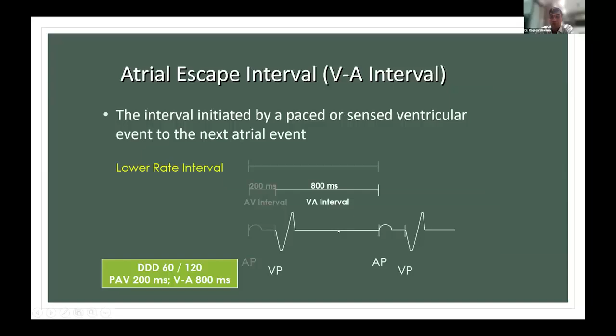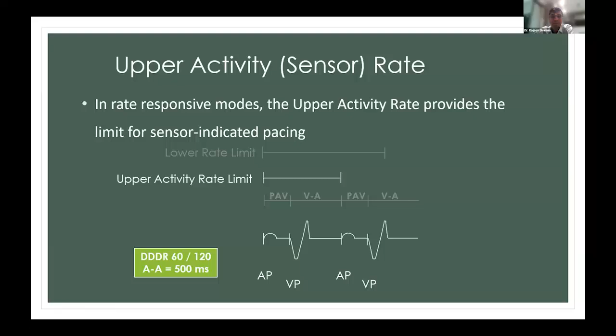There are two terms which are commonly confused: upper sensor rate and upper tracking rate. First is the sensor rate. It is the uppermost rate which is decided by the sensor of the pacemaker according to the body's needs. Suppose a patient is walking, then the rate will increase, and if running, then it will increase more. So the sensor of the pacemaker will sense and decide the rate. It is usually programmed higher in young patients and physically active patients. In this case we can program it around 120, but in a young patient we have to program around 150.